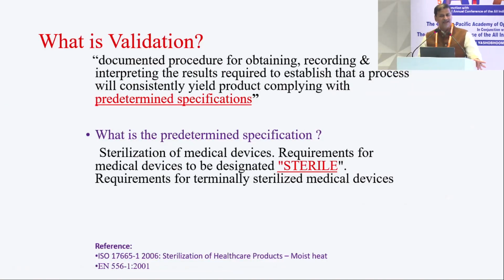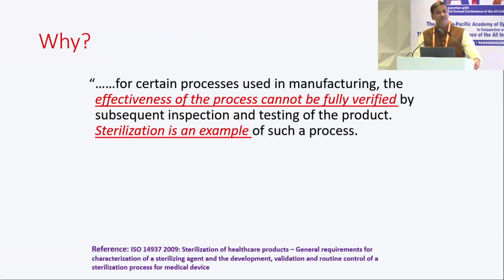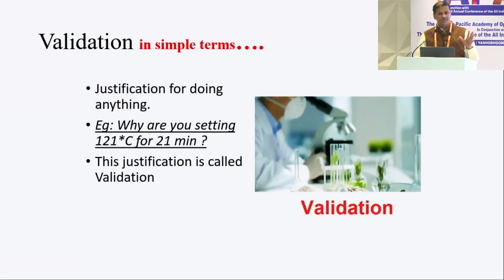So the next part is validation. What is validation and why is validation needed? This is a textbook definition of validation, but to put it simply, in a lot of manufacturing processes, just by looking at the product we would never be able to say that the process of sterilization has been done. For example, if you see an instrument, can you just say that this instrument is sterile or not? We cannot. So for this purpose, we have a lot of validation devices. For example, why are you keeping the temperature at 121 degrees Celsius and for 21 minutes? This is basically called validation.